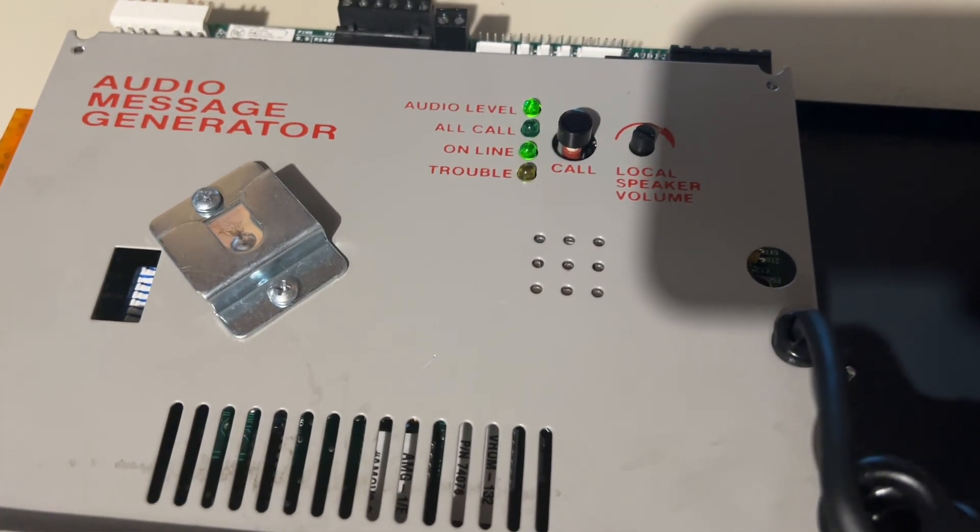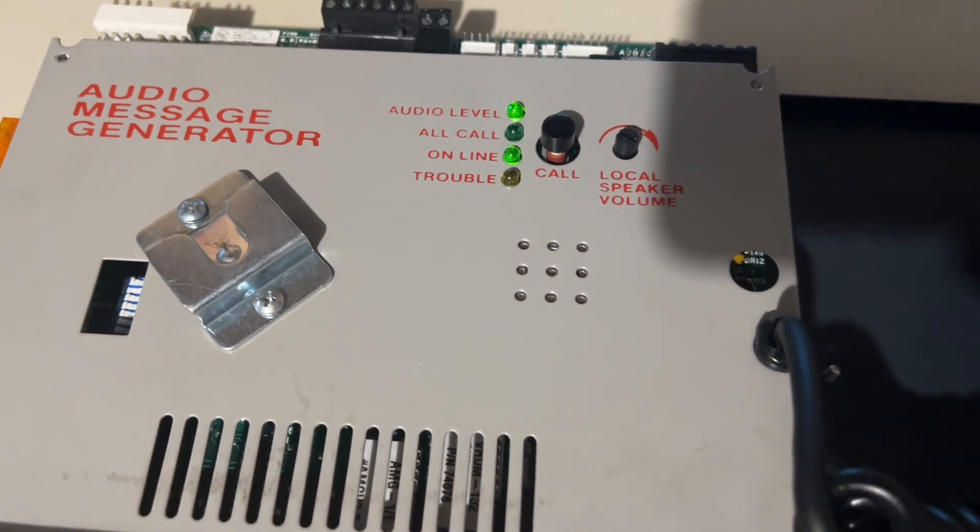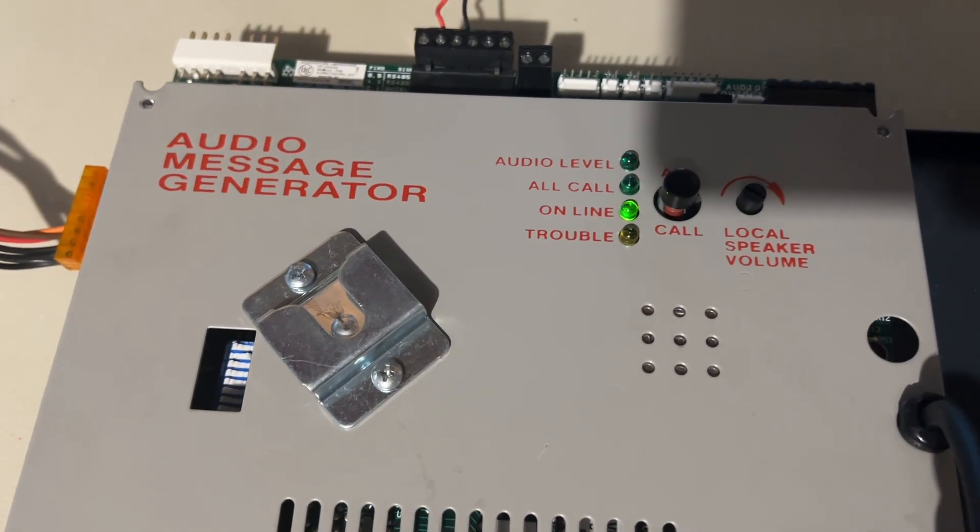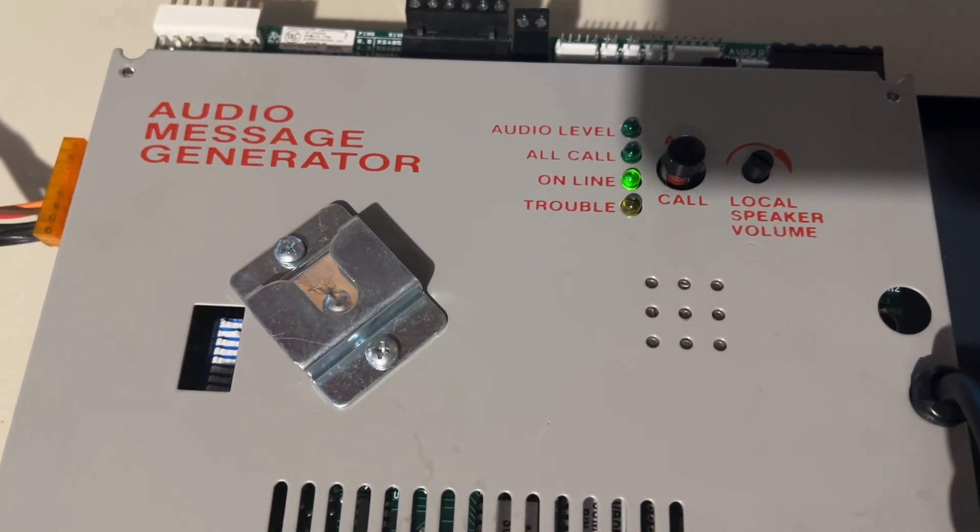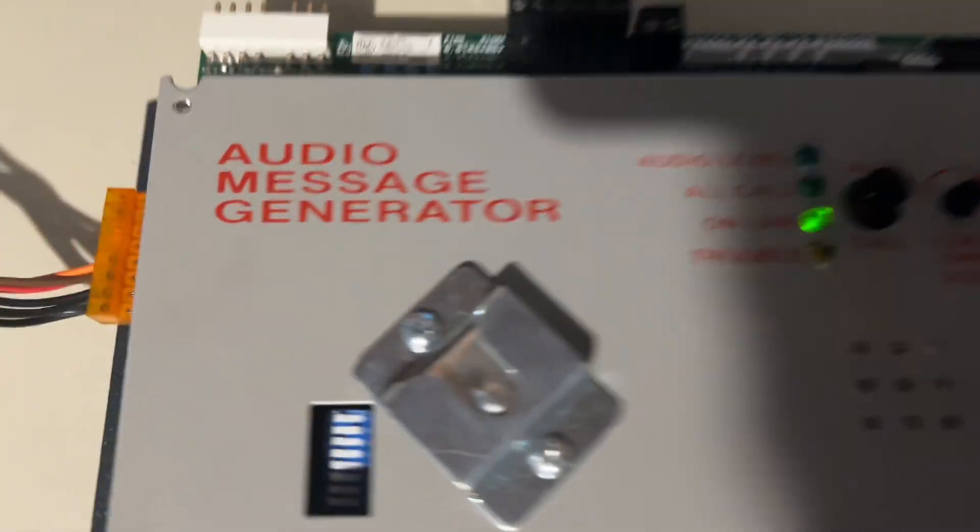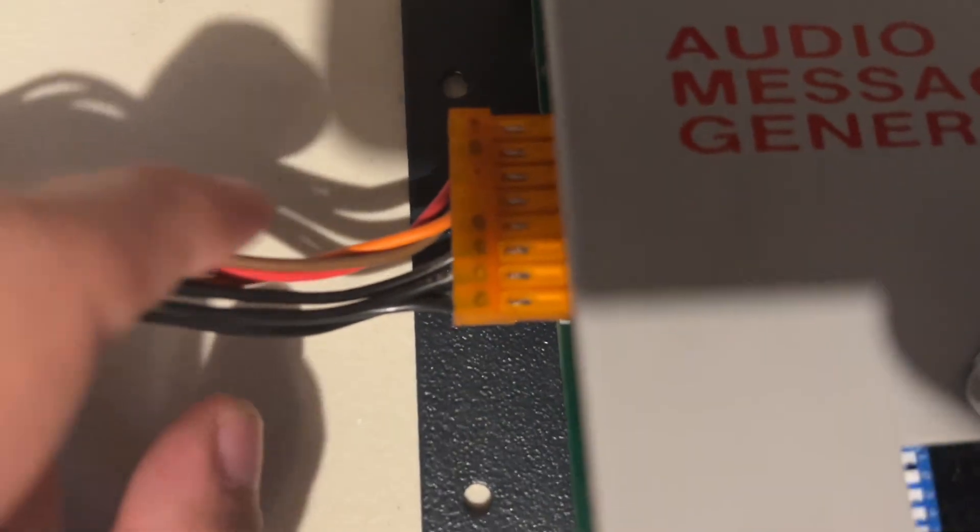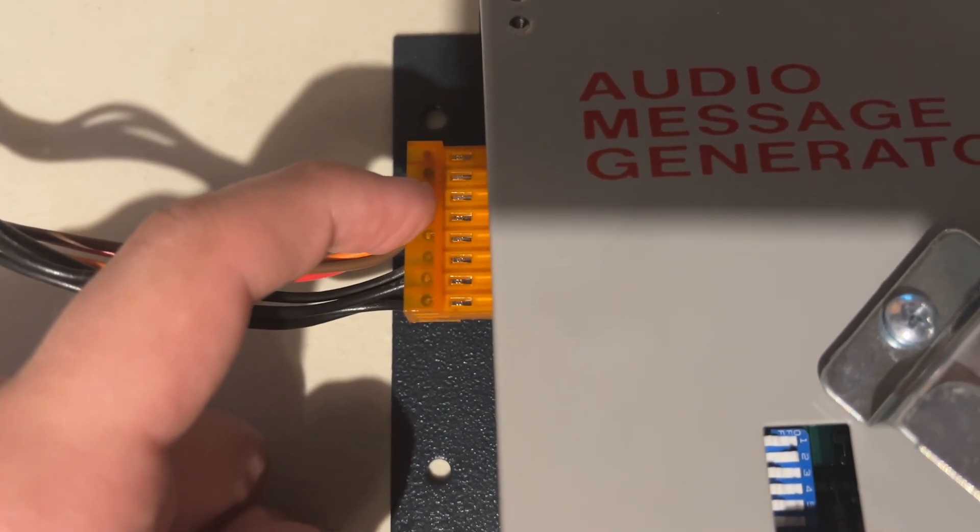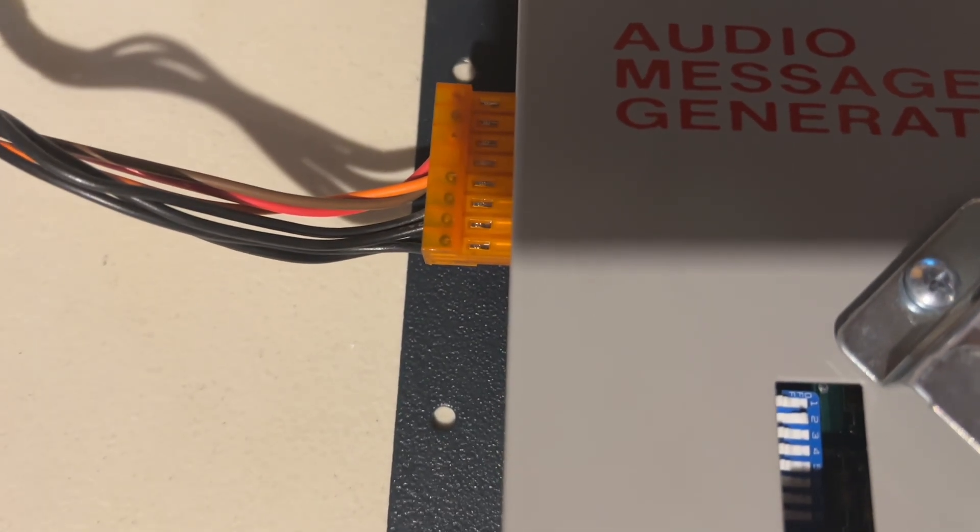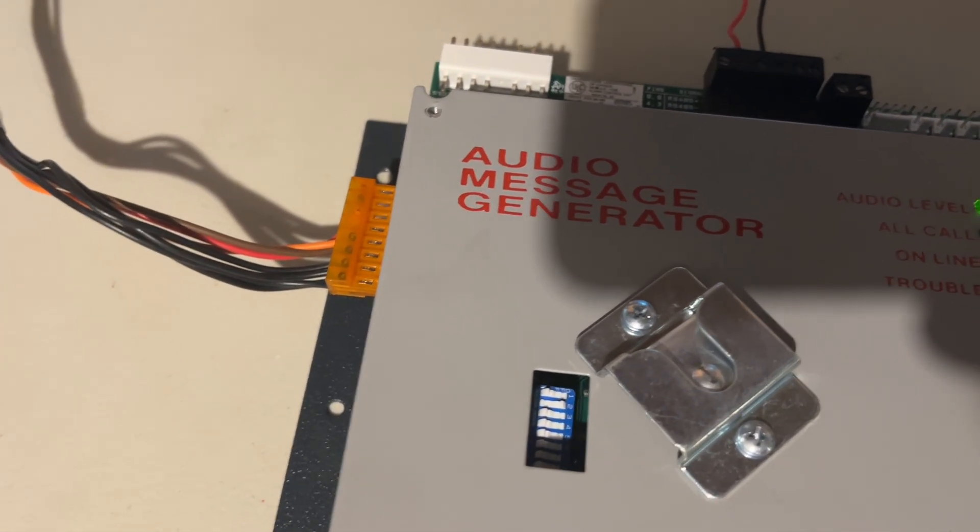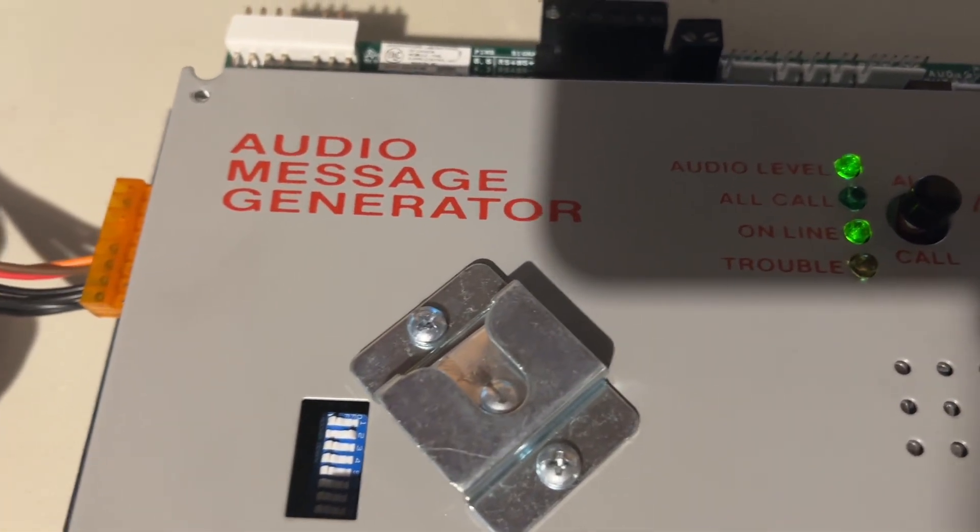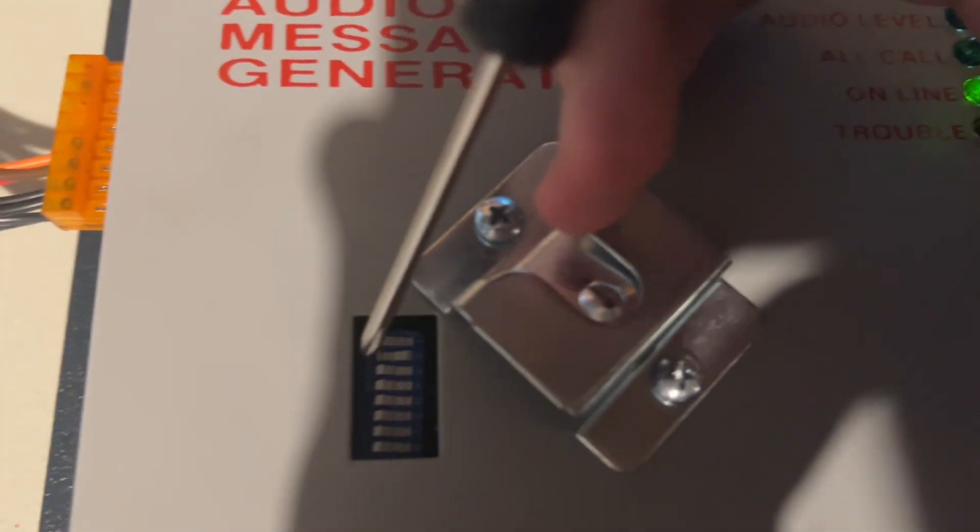Now the reason why I can't silence this is because it doesn't know that the system is in silence mode. It just knows that there's an alarm condition and that's kind of how these work on the AFP 300 and 400. What it does is it scans to see if there's an alarm or not and if NAC 1 is turned on. Now this panel can't transmit NAC status over serial. That's why I think this extra wire, I can't tell which one's which, but that's why I think that unmarked pin is a NAC input. Because on the 300 and 400, the NACs are on the power supply. So it could either be 5 volts or it could be 24 volts. I don't really know and I don't want to risk anything because I don't want to blow this up because it's expensive. That's why I think it can't properly silence because it doesn't have a NAC input. Just a guess. That's also why half the tones aren't available. But we can mess around with those by just changing the dip switches.